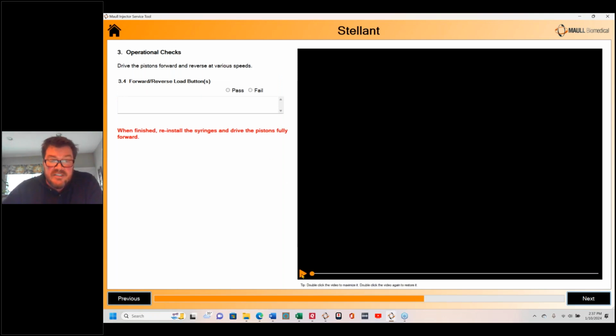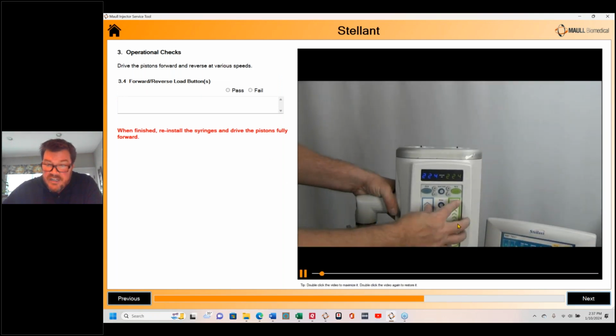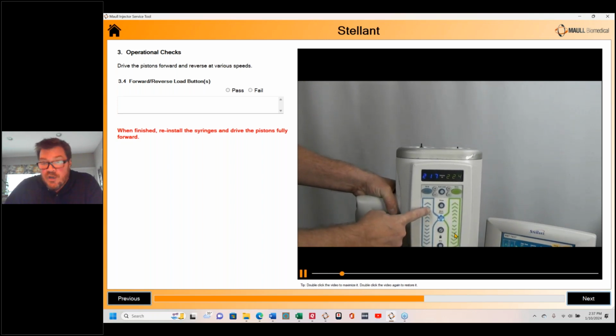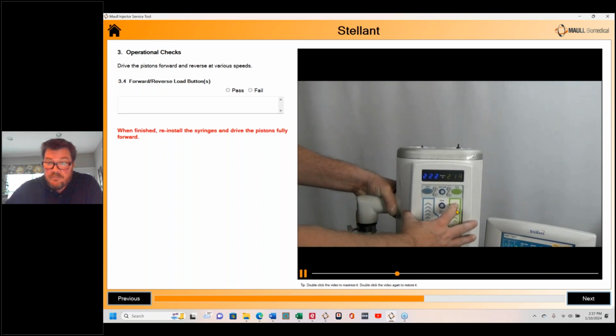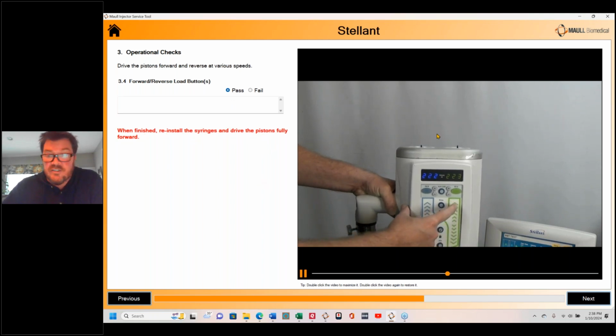Forward and reverse load buttons. We're just making sure that these right here are my forward and reverse load buttons, and that they work properly. Pressing up makes the piston move forward at various speeds. Same thing in reverse. We're on the blue side here, so that's saline. Then in a second, I'll move over to the contrast, the green side, and do the same thing. Just make sure the forward and reverse buttons work at various speeds. And it's pass/fail. When finished, reinstall the syringes and drive the pistons fully forward.